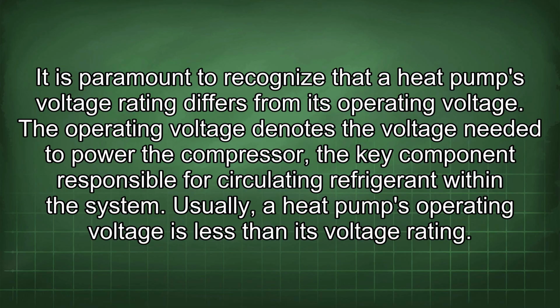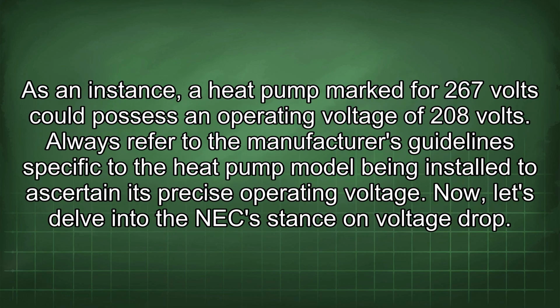It is paramount to recognize that a heat pump's voltage rating differs from its operating voltage. The operating voltage denotes the voltage needed to power the compressor, the key component responsible for circulating refrigerant within the system. Usually, a heat pump's operating voltage is less than its voltage rating. As an instance, a heat pump marked for 267 volts could possess an operating voltage of 208 volts. Always refer to the manufacturer's guidelines specific to the heat pump model being installed to ascertain its precise operating voltage.